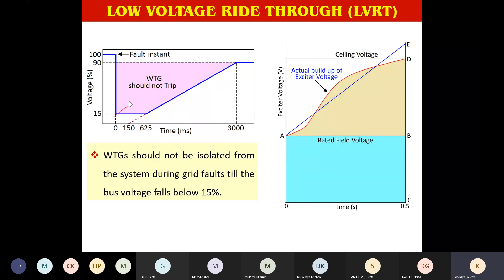In synchronous machines, it is there, and whenever the voltage falls, in typical power plants, the excitation system has a facility called field forcing or field boosting, so that the power flow from the machine will be adjusted using this field forcing. But there is no such facility available in the case of renewable resources. But here it should not disconnect immediately. It should wait till the voltage falls to a set minimal level. After that also, a certain time delay is there. So it is basically to support the grid.